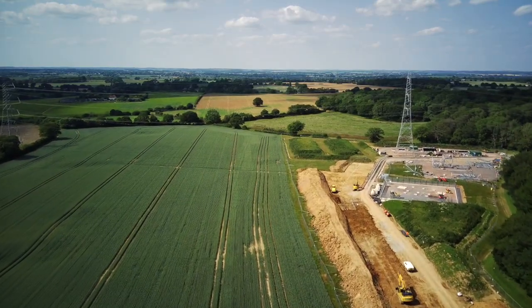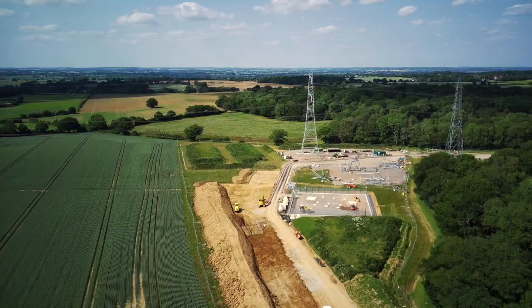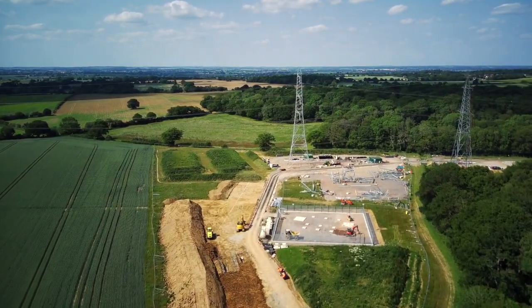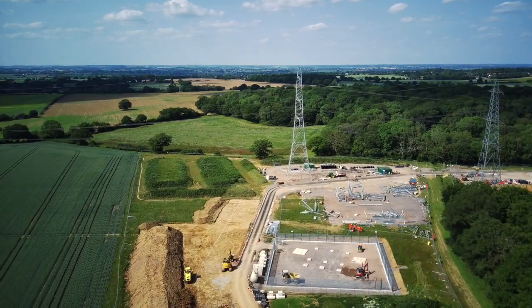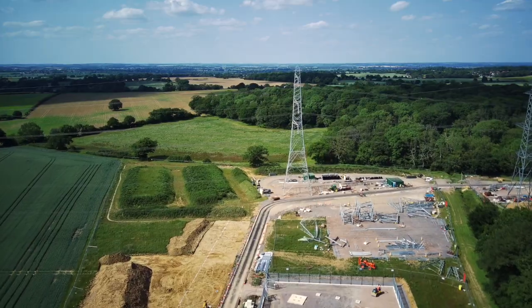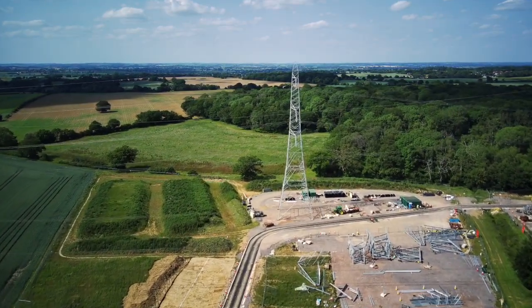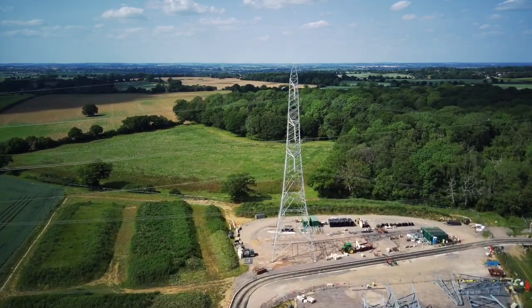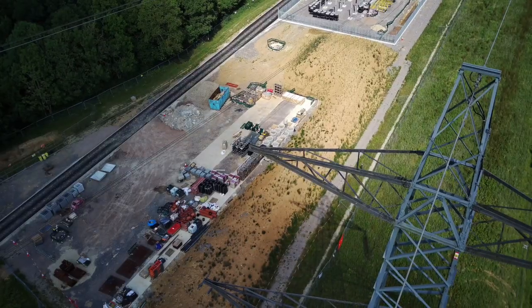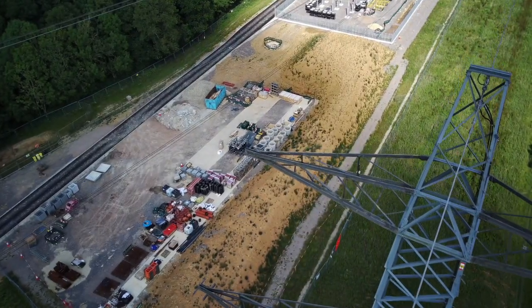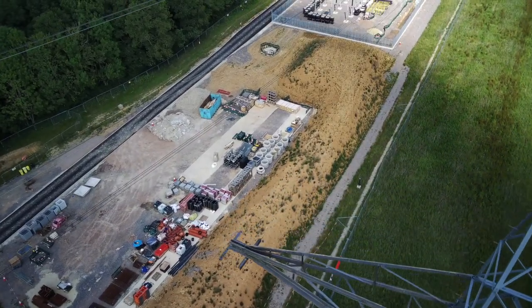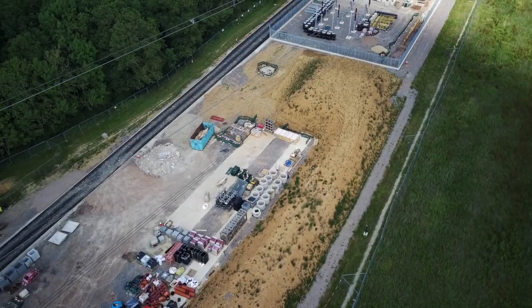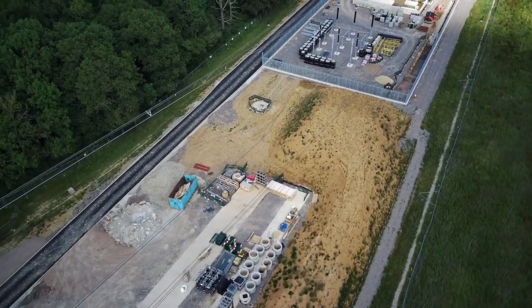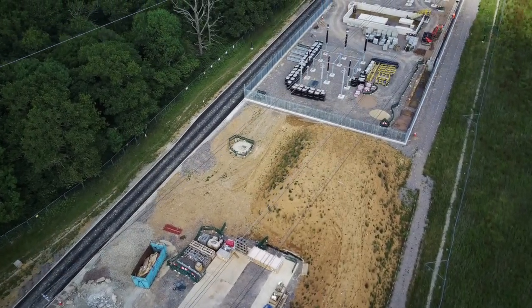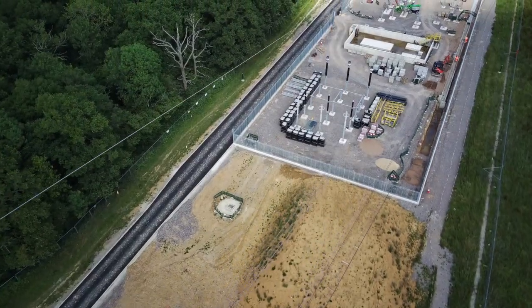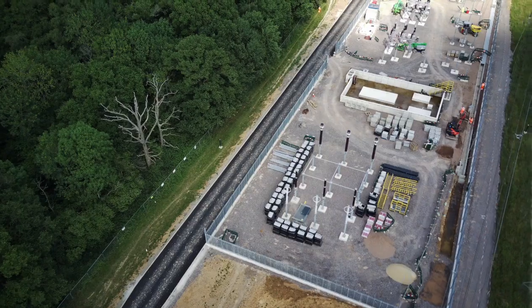Now as we turn to the right towards the main part of the substation, you can see an old 400 kilovolt pylon, very dark now, galvanized structures. The shiny new one straight in front of us is taking the northern circuit, and that will be a sealing end compound, meaning it will take a set of overhead wires and convert them down to underground cables. Those cables will pass along the site, past this storage compound, into the substation proper, and connect via equipment on the ground to the second supergrid transformer, which will be within those walls.